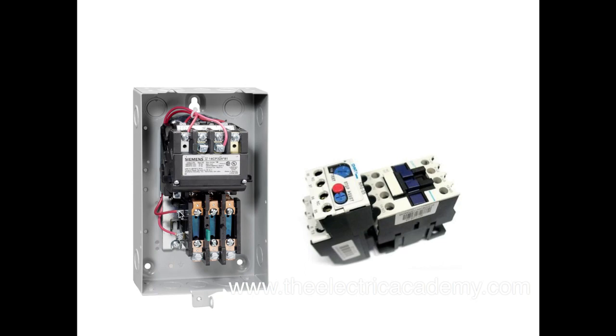Right down here, this would be your normally closed contacts for your overloads. You're seeing more and more of this style - this is IEC, which is a European style. They're smaller and more compact, not as robust, but they're generally in motor control stations anyways. Same thing: you've got line one, line two, line three. Here's your normally open contact, here's the other side of the normally open contact, and over here you've got your overloads. Down here if you can read it: T1, T2, T3.